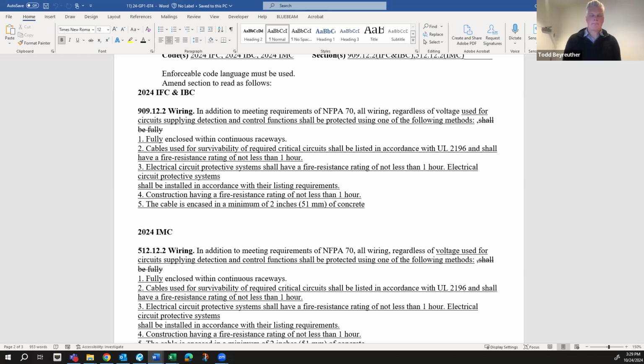Thank you, Michael. Andy? So I do happen to have some experience with these requirements. Options 2, 3, 4, and 5 are mostly about the rating of the cable. The original language in IBC and IFC section 909.12.2 talks only about protection by continuous raceways as required by or as defined by NFPA 70, but it does not talk about the requirements for the rating. I believe the intent here was to add options 2, 3, 4, and 5 as an additional option in lieu of providing continuous raceways only, the non-rated continuous raceway for NFPA 70.